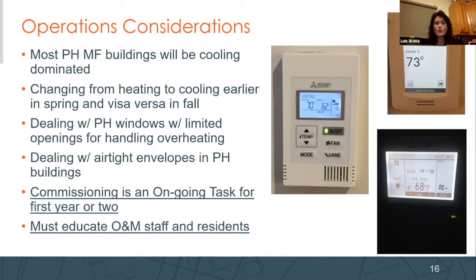Operations consideration. So as I said before, most of our multifamily buildings will be cooling dominated. They usually have set times when they don't have heat recovery that they change over from cooling to heating, and then in the spring from heating to cooling. It depends on what you're obligated to do for cooling, but you may want to extend that cooling window. So if you normally turn over from cooling to heating October 1st, you may want to consider November 15th.